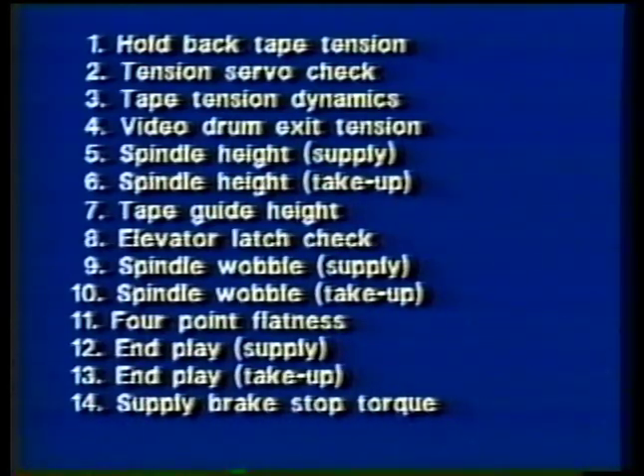This is something that you'll see our spindle height gauge will perform. Guide height, also with the spindle height gauge, we'll be able to check a number of guides in the tape transport universally. The elevator latch check, this is a very important function we'll get into very shortly. It shows if the elevator is latching down, holding the cassette properly in the machine. Spindle wobble on the supply, spindle wobble on the take-up have to do with the performance of the actual spindles. We'll again demonstrate those. 4-point flatness has to do with the 4 pins that support the cassette. The end play is up and down of the spindles, both on the supply and the take-up.